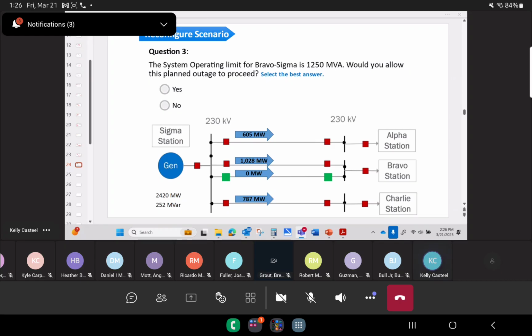And we were really, really close to just tripping the high side breaker and tripping that unit offline. I mean, if you get to that point where you've got everything dispatched to minimums that you can, and load continues to drop, and your ACE is going really positive, frequency is going high, yeah, you've got to do something. And if it gets to that point, then yeah, you're going to have to take a generator offline. In most cases, that would just be a dispatch. You just dispatch somebody to go to zero.